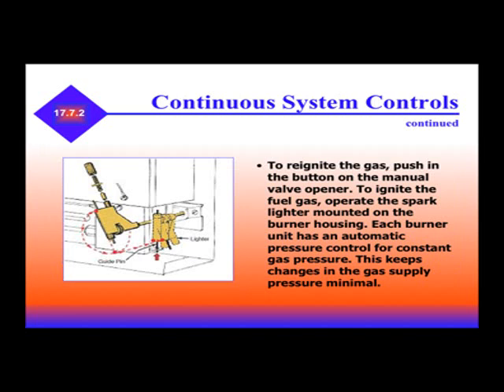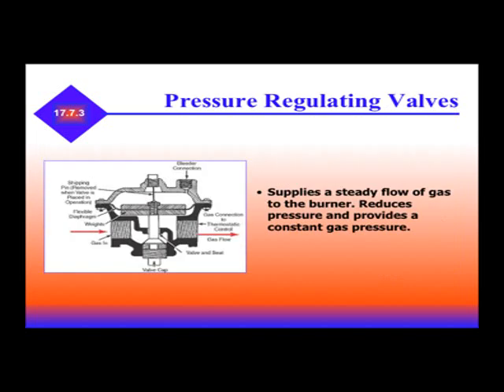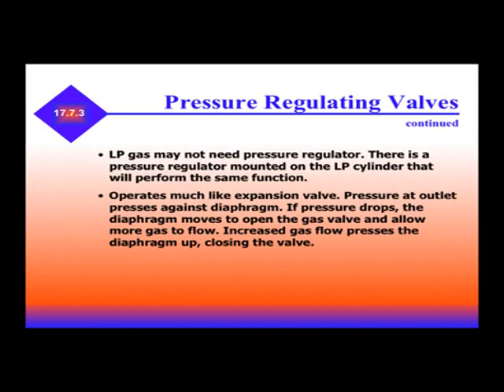To reignite the gas, push in the button on the manual valve opener. To ignite the fuel gas, operate the spark lighter mounted on the burner housing. Each burner unit has an automatic pressure control for constant gas pressure, keeping changes in gas supply pressure minimal. Newer units may have a tilt control system that senses when the unit is not level and diverts heat away from the generator. When leveled, heating begins again. Constant level changes may result in blockage or shutdown of the absorption system. The pressure regulating valve supplies a steady flow of gas to the burner. LP gas does not need an additional pressure regulator, as a pressure regulator mounted on the LP cylinder performs the same function.